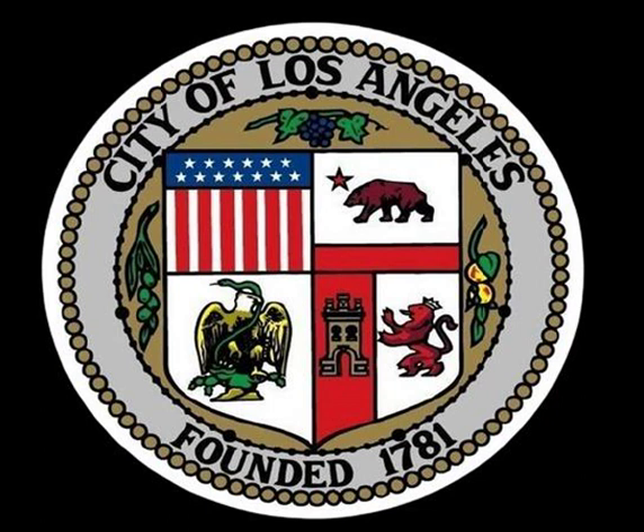The Pacific DC Intertie, both poles, were out for about 21 hours. The first 500 kV line was the Victorville-Rinaldi line, which relayed 6 times during this event. The last time we left it out because there was just too much smoke, and it was out for about 9.5 hours. The Adelanto-Rinaldi, another 500 kV line, relayed a total of 2 times and was also left out for about 9.5 hours.